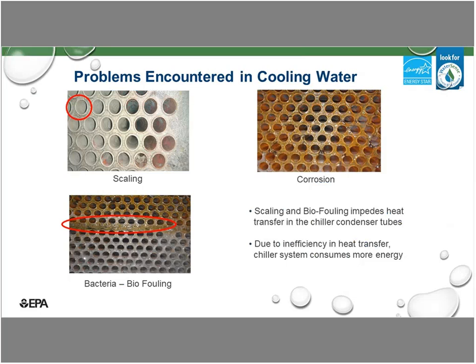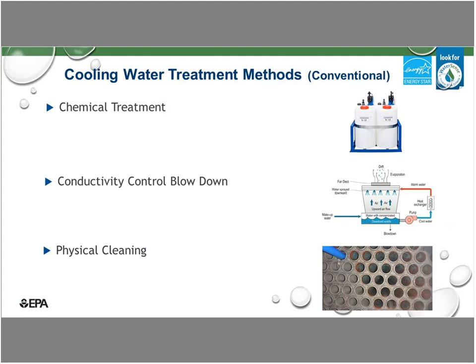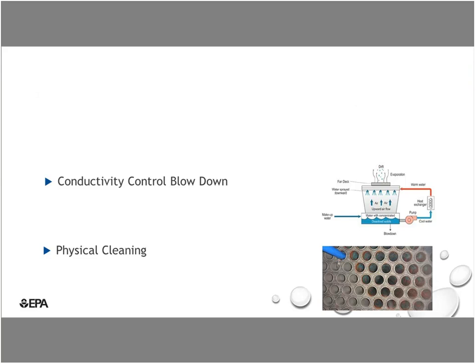Okay, the conventional methods, which were also mentioned by Robbie, involve chemical treatment. You manage the conductivity and do your blow down to ensure that the minerals in the water do not cross the solubility line. Once it crosses the solubility line, that's where you get scaling. You also need to maintain a certain pH to prevent corrosion, and add chemicals to treat the bacteria to prevent biofouling. Of course, the other kind of bacteria that they are most concerned about is the Legionella bacteria, which can be quite deadly.